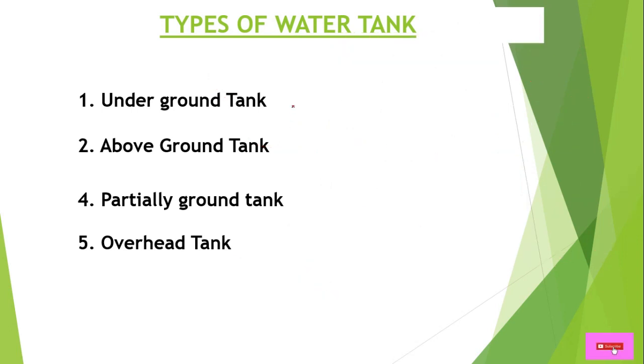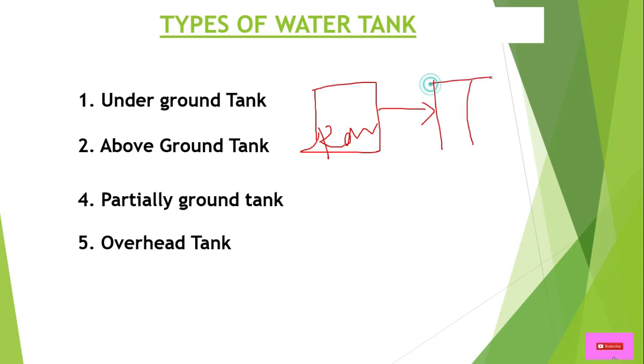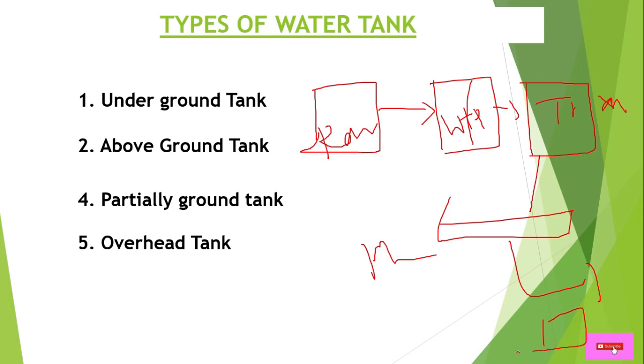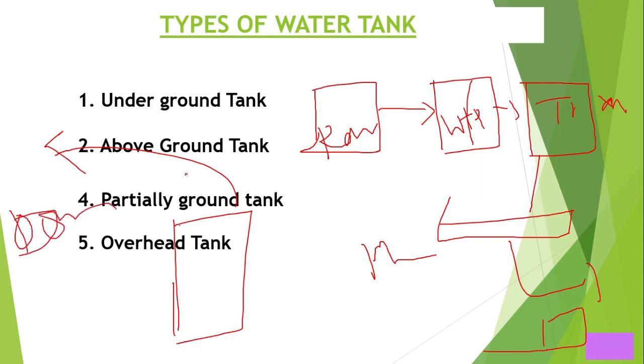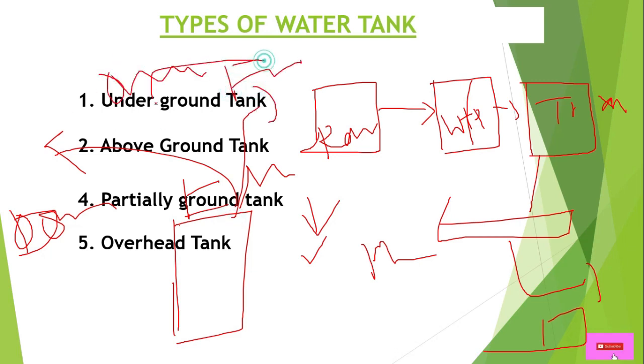We cannot feed raw water directly to the building plumbing fixtures for drinking or bathing. So we take the raw water tank water through a WTP — Water Treatment Plant — and after treating it, feed it to a treated water tank. From there we distribute water through a hydropneumatic pump to plumbing fixtures. Above the building we have a domestic overhead tank, a flushing tank for WC use, and an overhead fire tank for use in case of pump failure.